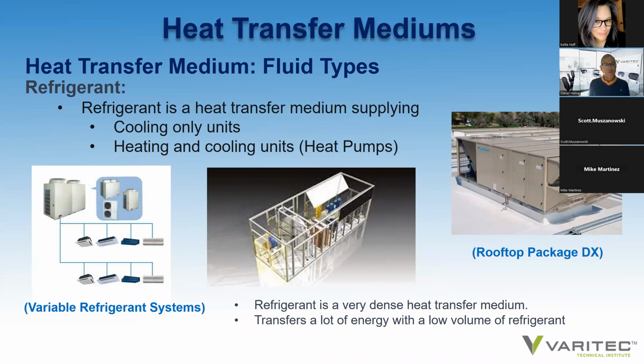So what about refrigerant as a heat transfer medium? Well, it's excellent because it's so dense. And this is why variable refrigerant systems are gaining momentum, because they supply the refrigerant local to each building zone, so you're not pumping all the air throughout the building to do so. And so refrigerant is a very excellent, efficient method of heat transfer that should be considered for high efficiency buildings.